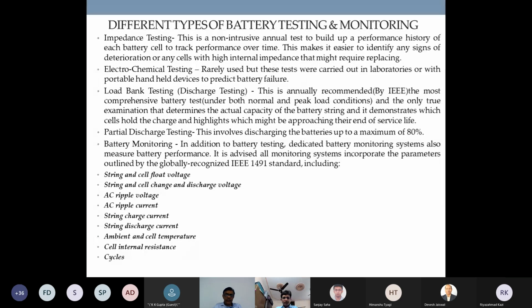Different types of battery testing and monitoring - how we test the batteries: impedance test, load bank test. Load bank test is extensively used by everyone having this storage, to determine what will be the capacity after say 1 year, 2 years, and it is mandatory, even mandated by IEEE, to carry out this load bank test.